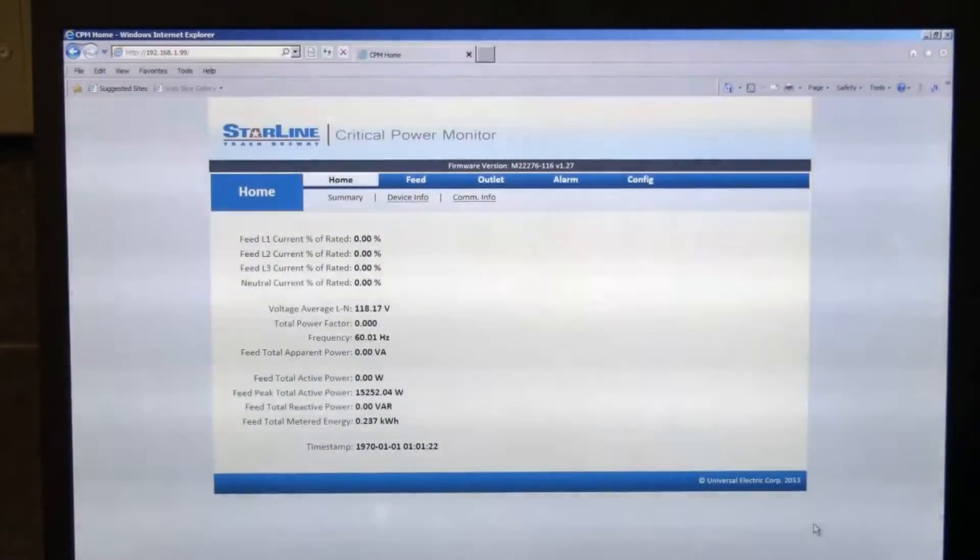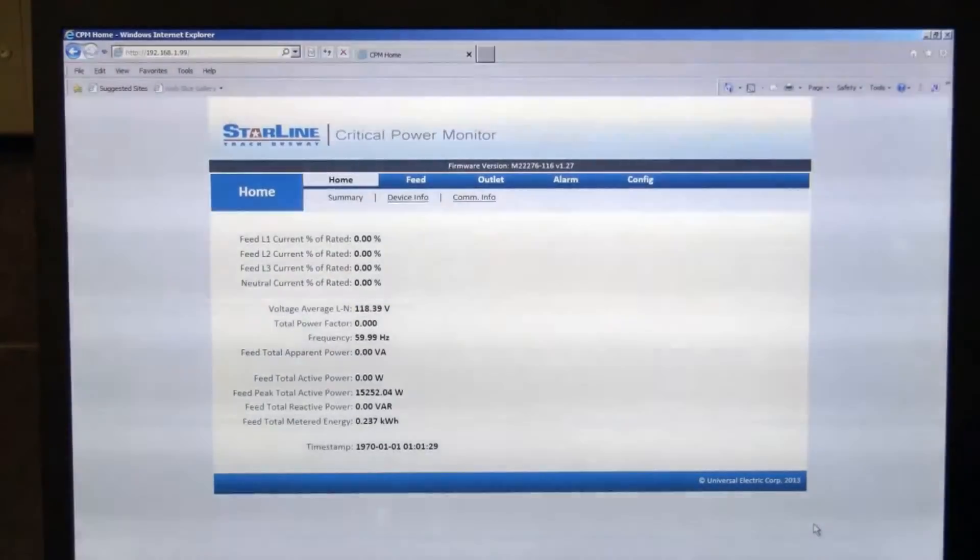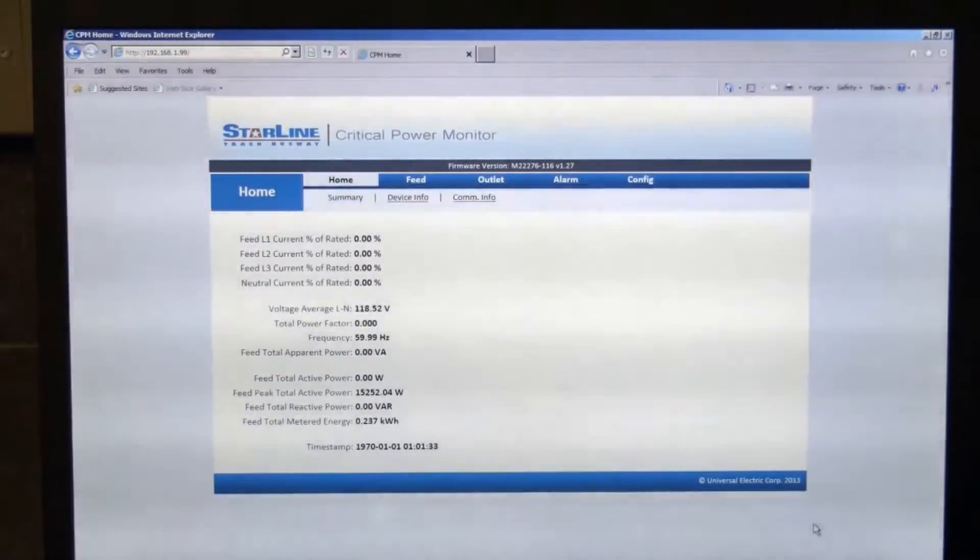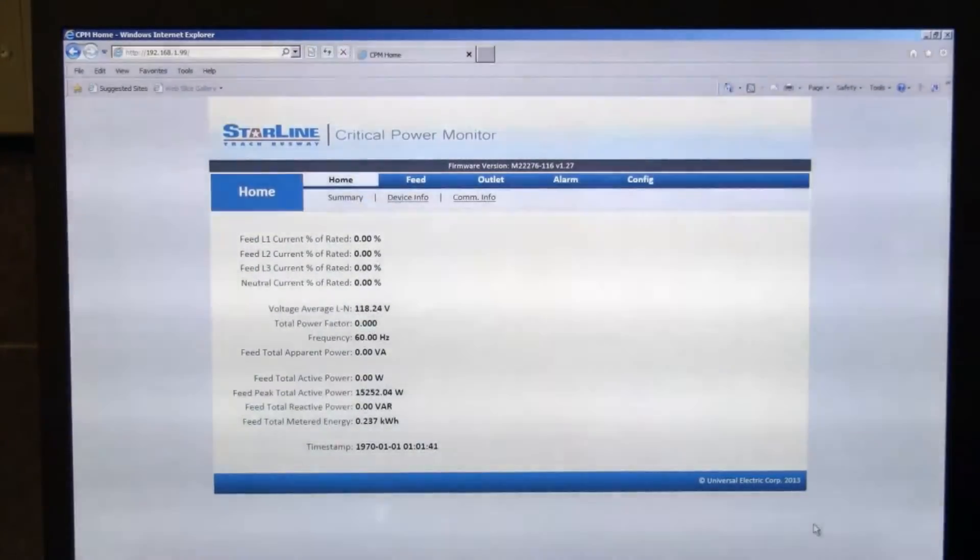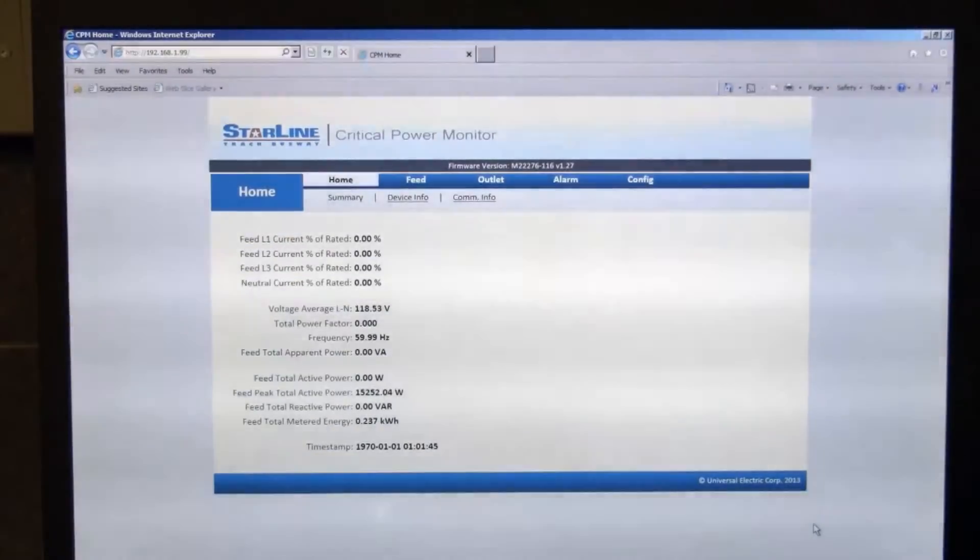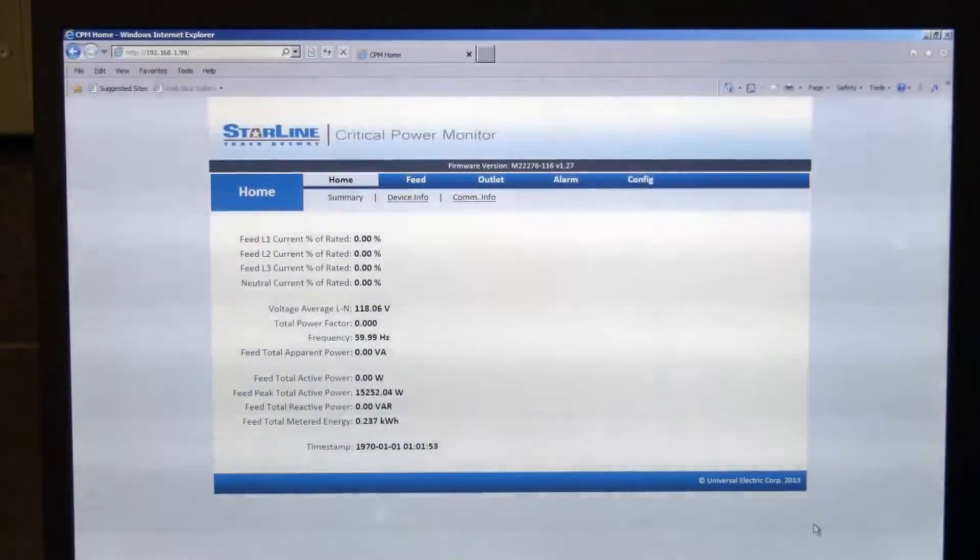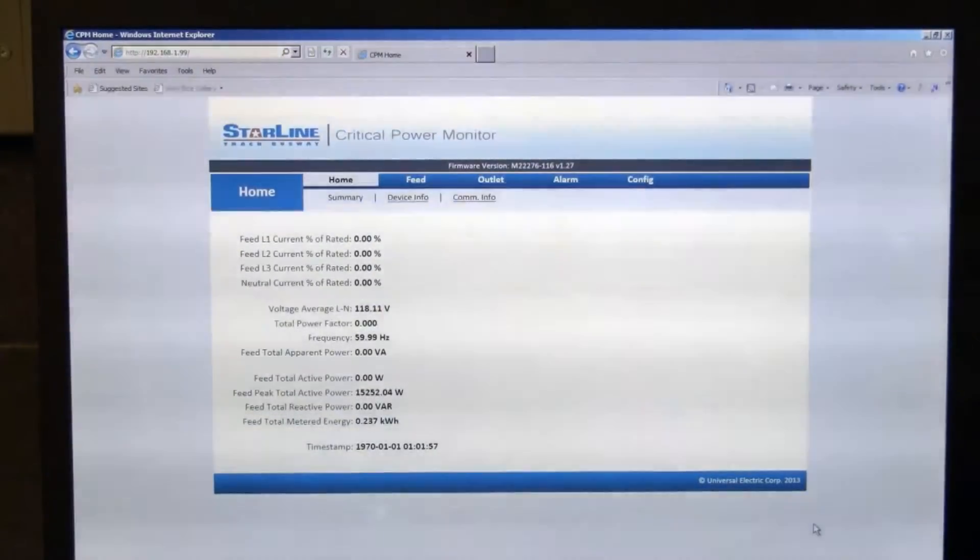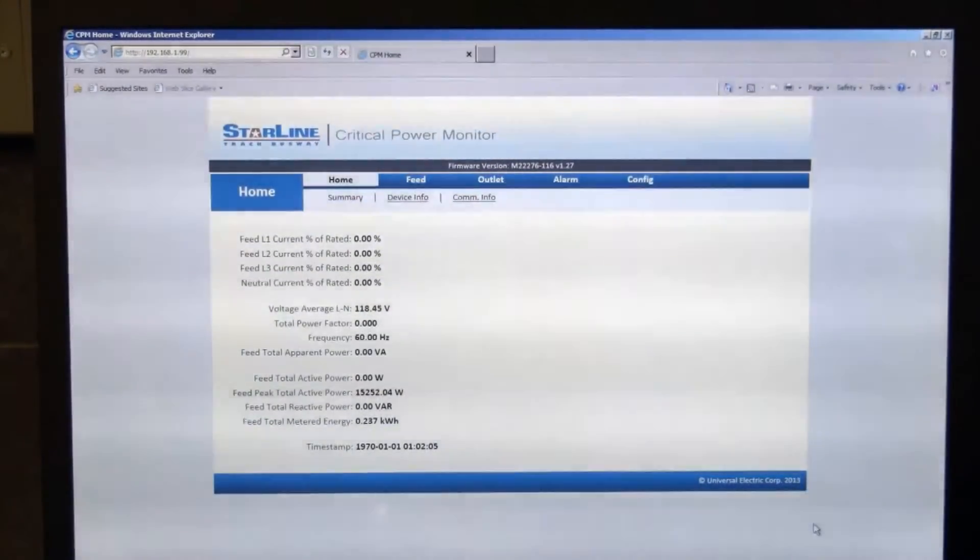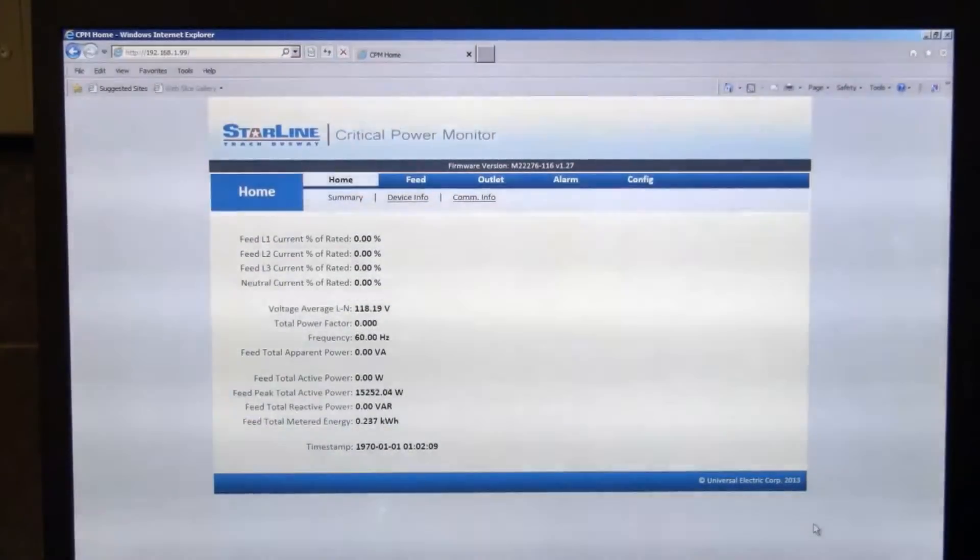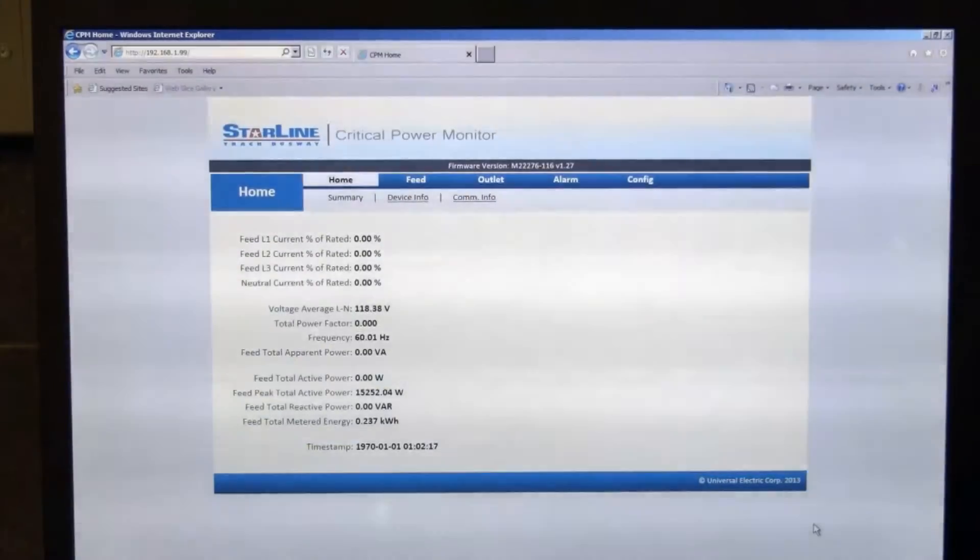This is the mechanism by which you can change your IP address information, which we'll show you both on the wired port and the Wi-Fi, set your Modbus address for people implementing a Modbus RTU scenario. You can look at the various feed outlet configurations depending upon whether this is a branch circuit or end feed application. You can look at your outlet-by-outlet configurations as well if it's a plug-in unit that has multiple outlets configured within it. You can set alarm conditions, and then you can also go to the configurations tab which has a myriad of features, upgrading firmware, changing other information, things like that which we'll talk through. You can see here, this is set up like you would see a typical Ethernet based device with your tabs up at the top that you can scroll through, and then once you're on a particular tab there are sub tabs underneath those categories as well.